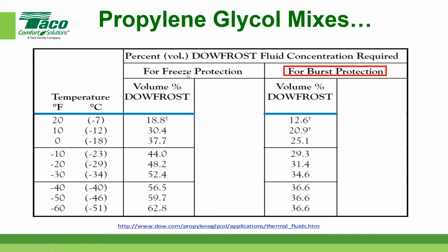The freeze column is for things like a normal application where you're running really cold fluids. For instance, under a design condition, I normally am pumping minus 30-degree fluid. Okay, if I wanted to do that and not have any ice crystals show up, hence the name freeze, then I would need 52.4% Dowfrost mixture or propylene glycol mixture. That would keep that from happening. That means all day long I could pump minus 30-degree product.